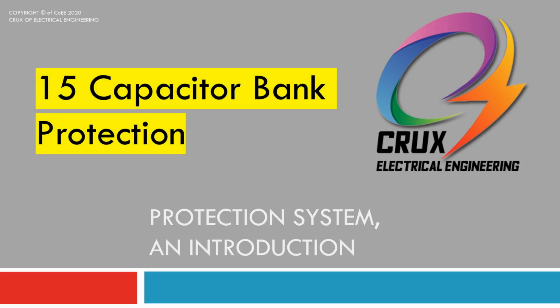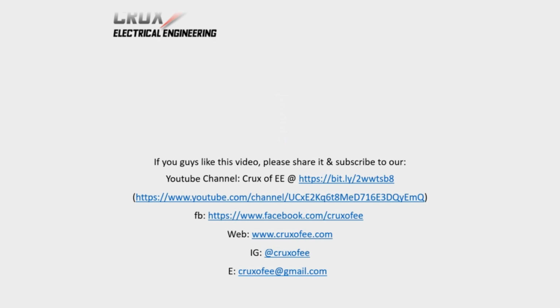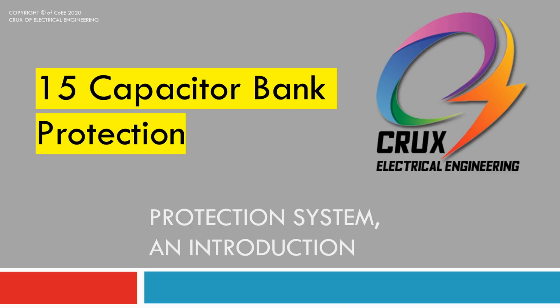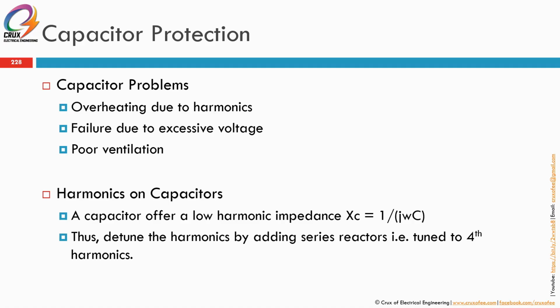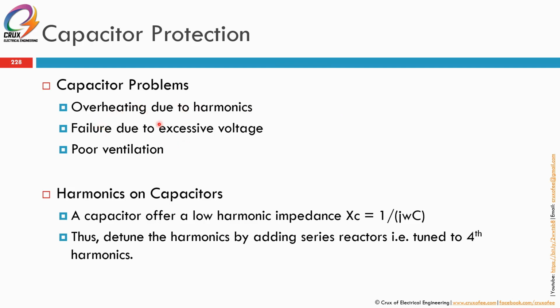Topic number 15 is on Capacitor Bank Protection. So capacitor protection. Before knowing what kind of protection we require, let's see the typical problems that the capacitor faces. Capacitor problems: overheating due to harmonics, failure due to excessive voltage, and poor ventilation, which is a cooling issue, and heating of the capacitor. Eventually once it overheats, it will deteriorate the insulation, and flashover or short circuit will happen.